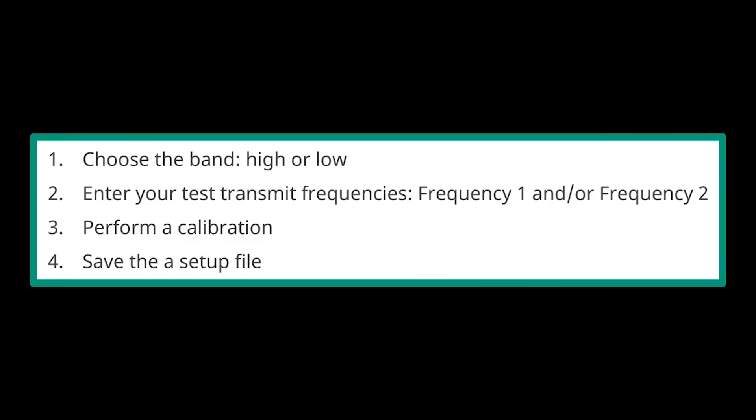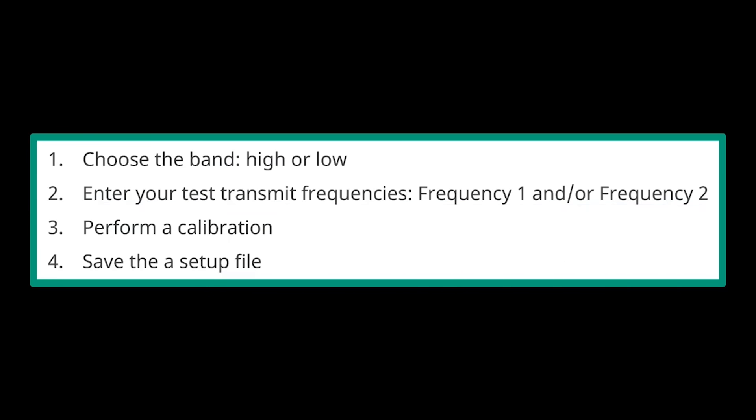To create setups for non-default transmit frequencies, first choose the band, high or low. Second, enter your test transmit frequencies, frequency one and or frequency two. Third, perform a calibration. And finally, save the setup file.